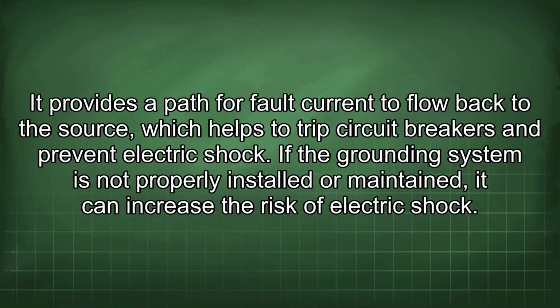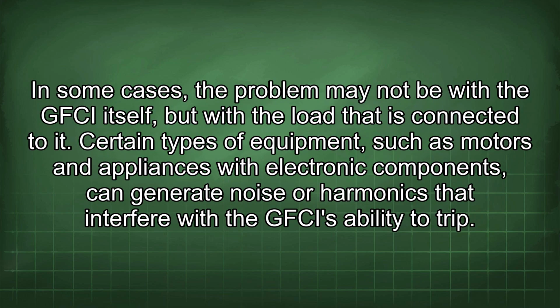It provides a path for fault current to flow back to the source, which helps to trip circuit breakers and prevent electric shock. If the grounding system is not properly installed or maintained, it can increase the risk of electric shock. In some cases, the problem may not be with the GFCI itself, but with the load that is connected to it. Certain types of equipment, such as motors and appliances with electronic components, can generate noise or harmonics that interfere with the GFCI's ability to trip.